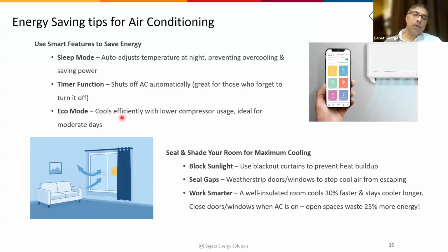Second, how are you reducing the heat load in the room? The external heat addition can be reduced by providing blinds or curtains. Any leakages can also be arrested. If it's a room where frequent opening and closing of the door is happening, you can install an air curtain, a high-speed fan which will isolate inside and outside air. If it is a top floor, you can even use high SRI paint, which will reflect the heat from the sunlight, so that the heat load inside the room will be less, and hence the energy consumption will come down.